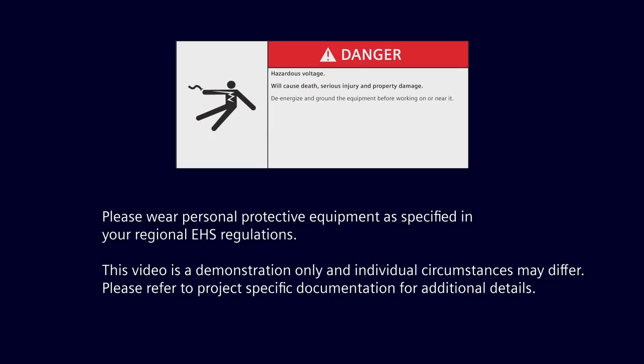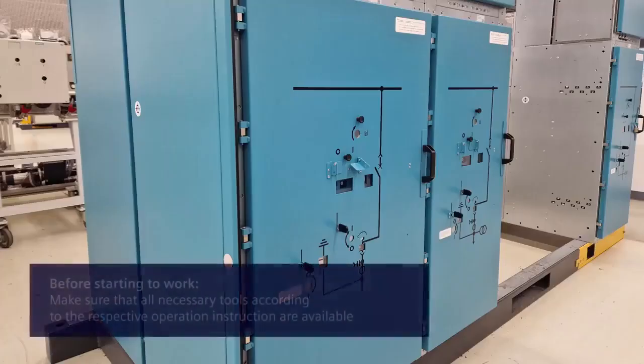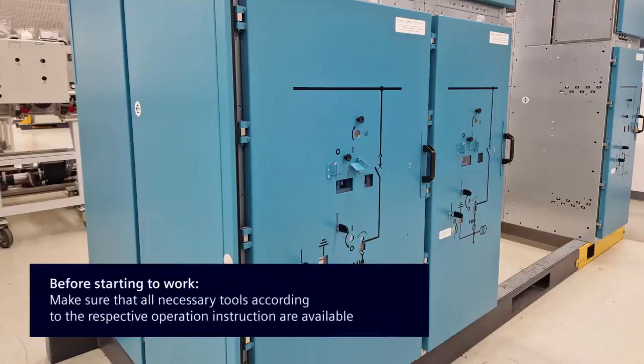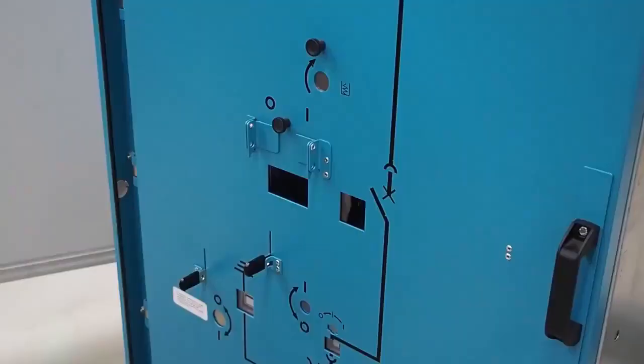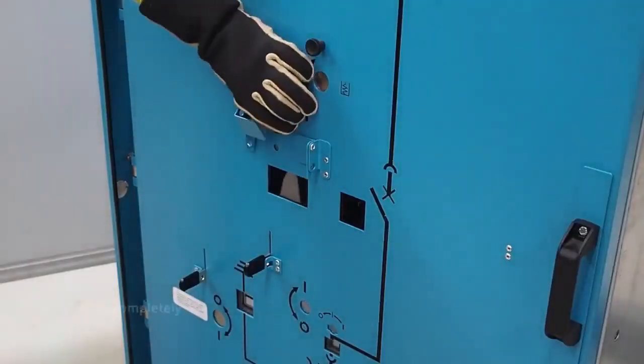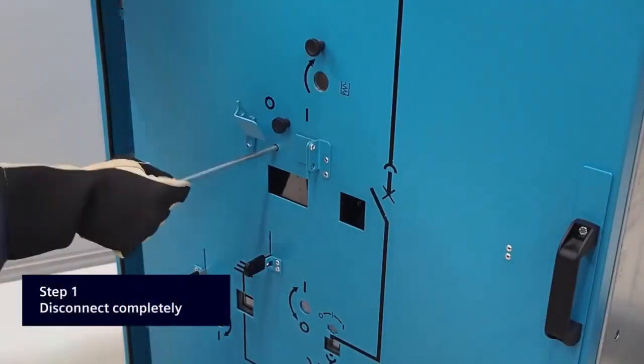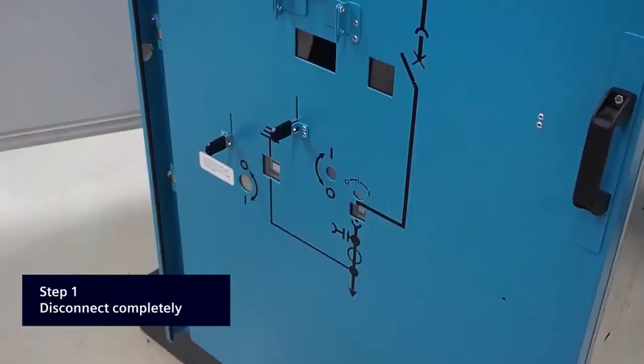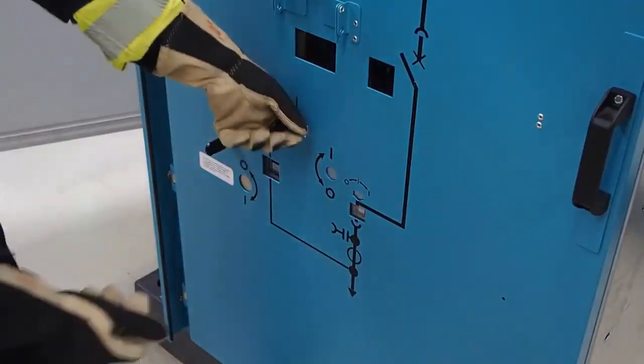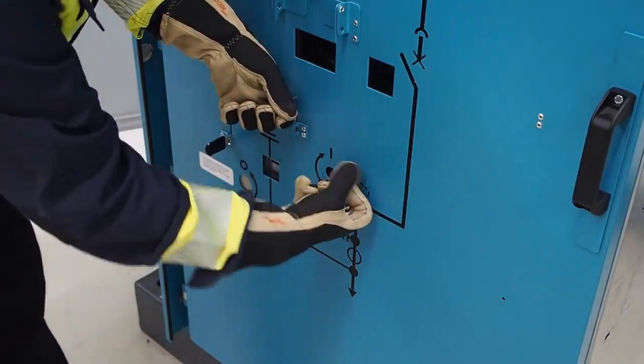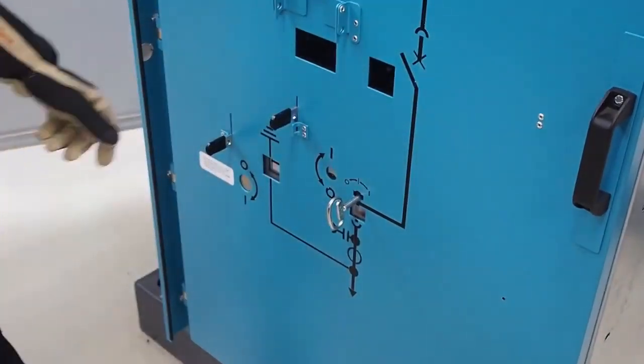Finally, use personal protective equipment in accordance with local laws and regulations, as well as other applicable EHS regulations. Before beginning any work, ensure that all necessary tools are available according to the operation instructions. The first step is to switch off the circuit breaker and make sure that the incoming feeder for energizing the busbar is switched off. Then withdraw the circuit breaker from its panel and place it in the test position.